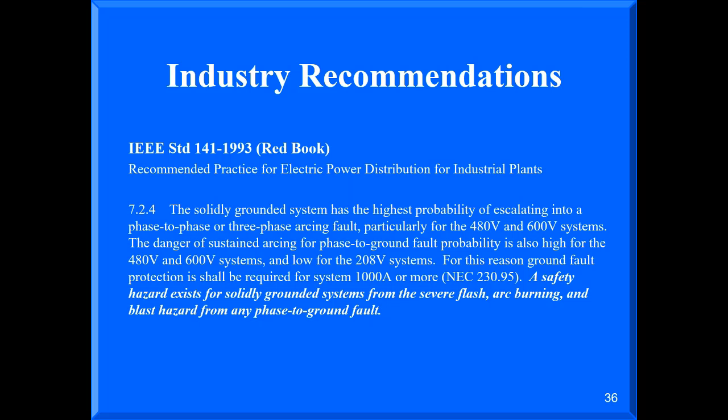So all of a sudden, this guy goes, I can't ever get the system restarted. What you're going to have to do is turn everything off, turn on the main, hope it doesn't trip, and literally, one by one, go start troubleshooting to find out where the fault is. That's the cheapest design by the NEC. It's what the codes require, but it is the cheapest design. Okay.